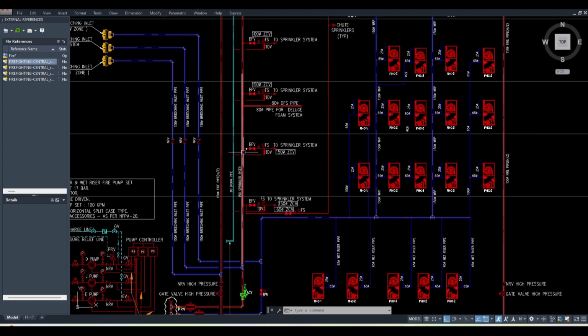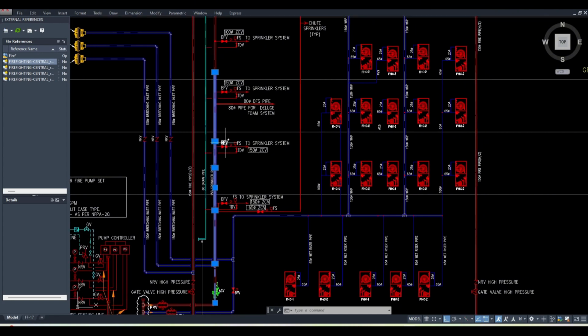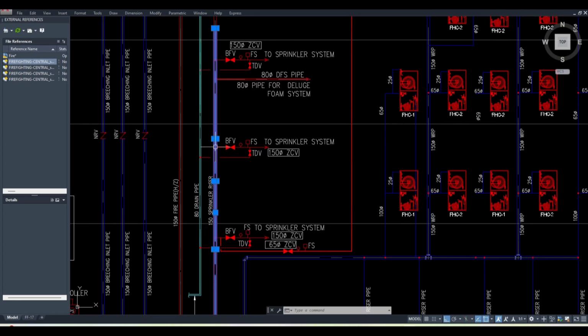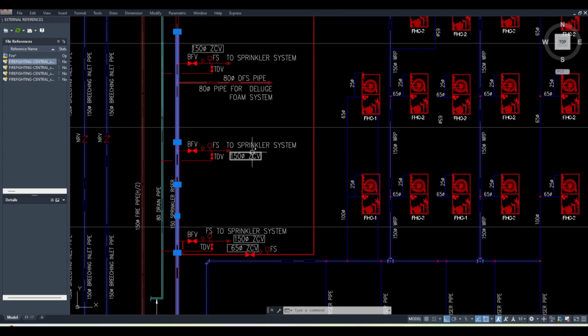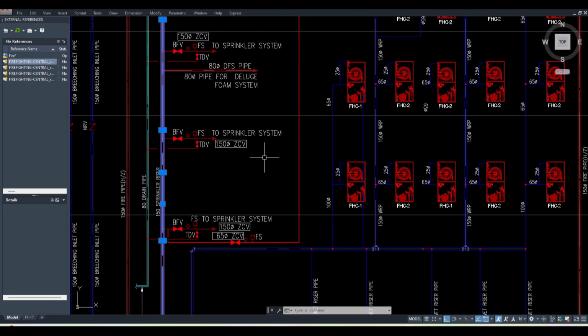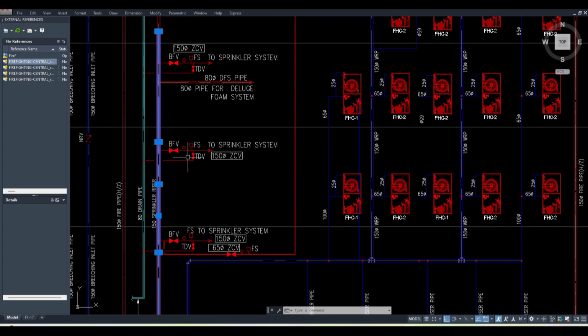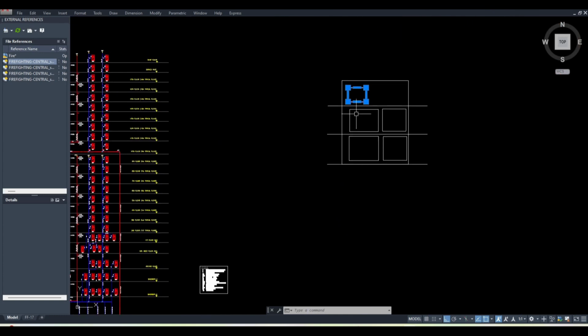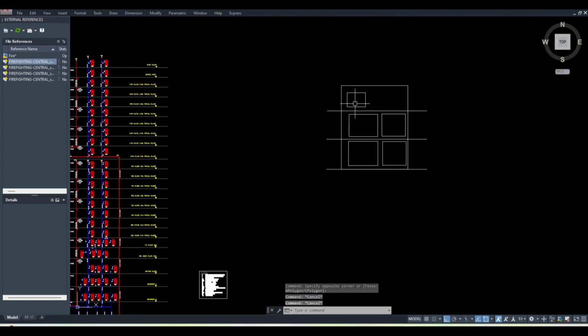Like the first riser is there, from the riser one pipe is coming out, and immediately when the pipe is coming out, you have to provide a fire zone control valve. Zone control valve, we call it ZCV. So ZCV must be provided immediately after taking the tap from the main riser, and then after that you can connect with the sprinkler. Correct. Now I'll come back to ZCV again, but before that, let's say one zone is there.